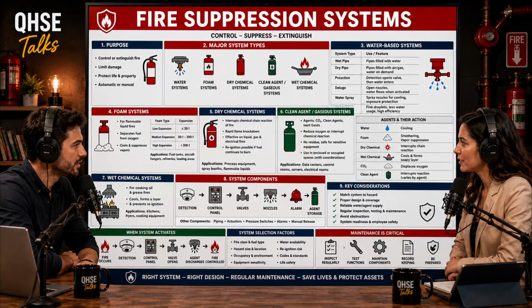Well, it's a combination of density and that expansion ratio we just talked about. Correct. Water is denser or heavier than most flammable liquids. So if you spray a solid stream of water onto, say, a vat of burning oil, the heavier water instantly sinks straight through the burning oil to the bottom of the vat. Right. But the oil at the top might be 500 degrees. So the water hits the bottom, instantly boils into steam, and expands 1,700 times in volume in a fraction of a second. Oh, wow. So it effectively creates a steam explosion at the bottom of the tank. Exactly. It violently erupts upward, blowing that 500-degree burning oil out of the vat and spraying it in all directions. You've basically just taken a localized fire and spread it across the entire room.